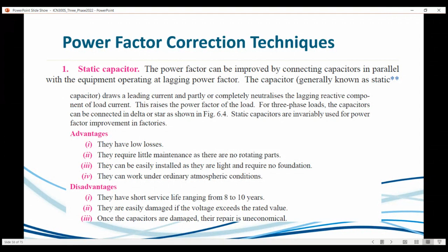But anyway, the advantages: they have low losses, little maintenance, and no rotating parts in the capacitor bank. They're light and can work in essentially any condition. The only problem is they have a short service life, arguably 8 to 10 years is quite fine, this could be shorter or longer. They are easily damaged if the voltage exceeds the rated value, and the repair is uneconomical, which essentially means you have to put in new capacitors.